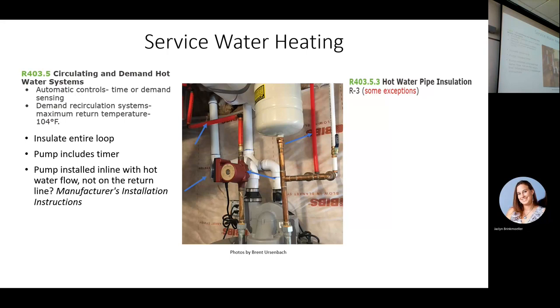Manufacturer's installation instructions are code. There are requirements that those instructions are on site for the inspections, that they remain with the equipment, because the manufacturer produces a product, takes it to a listing laboratory, has it tested in accordance with specific instructions, and then it receives a listing. If you don't install it in accordance with the instructions, you're not installing it in accordance with the listing, and you're violating the UL listing or whatever listing on that product, and they won't guarantee it, and it's not going to be safe or effective. And so the manufacturer's instructions are very important.